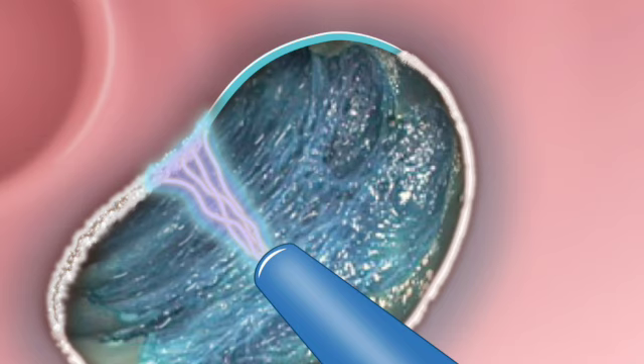Okay. That specific energy load creates a safe, superficial coagulation. It destroys the mucosa and barely grazes the submucosa beneath it. But if they keep their foot on the pedal for 3 seconds instead of 1... At that same 45-watt setting, a 3-second duration delivers 135 joules of energy. Triple the heat. Exactly. That heat load doesn't just spread out across the surface, it penetrates downward.